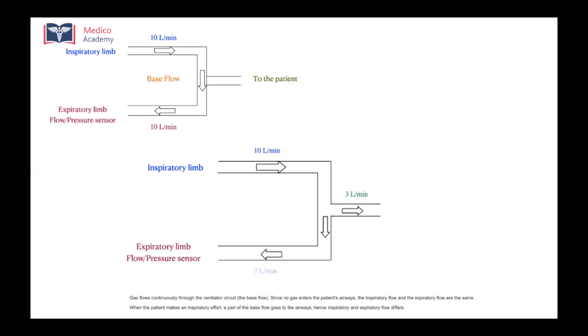Let's say 10 liters per minute was what was coming from the inspiratory limb. The patient has made an inspiratory effort and has drawn in flow at 3 liters per minute. So what goes back to the expiratory limb, where you have the flow sensor or the pressure sensor, will be 7 liters per minute. So there is a difference which occurs. It is this difference which is sensed by the ventilator, and the ventilator delivers a full mechanical breath to the patient.